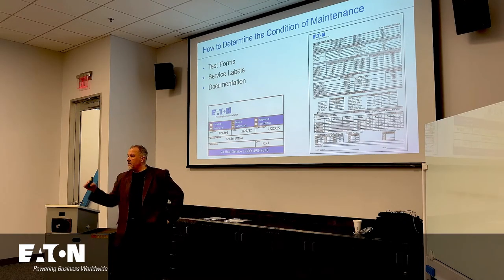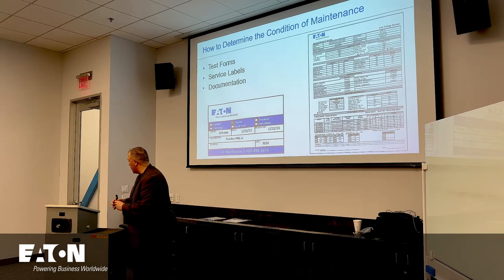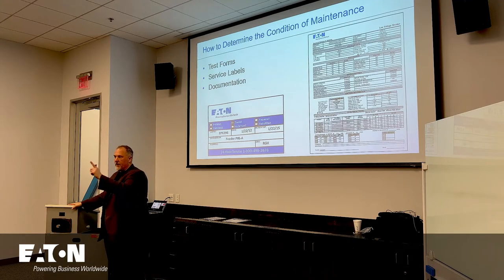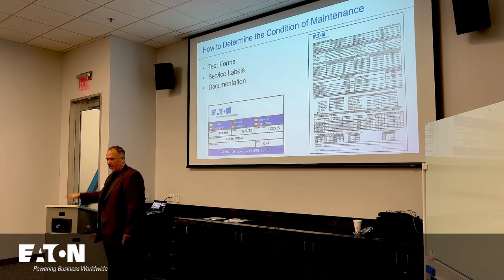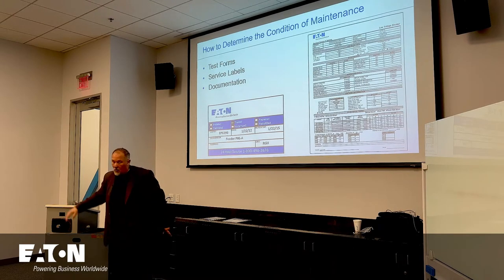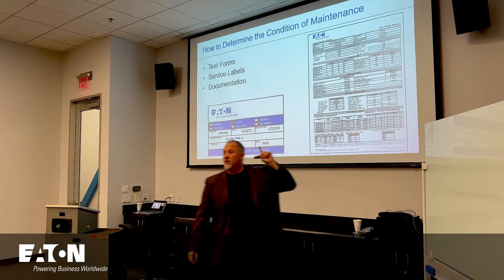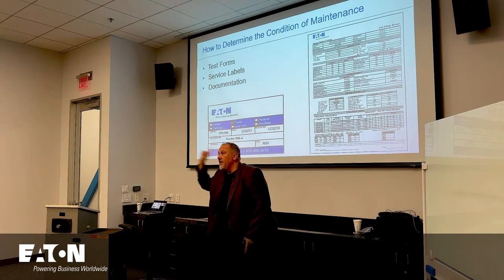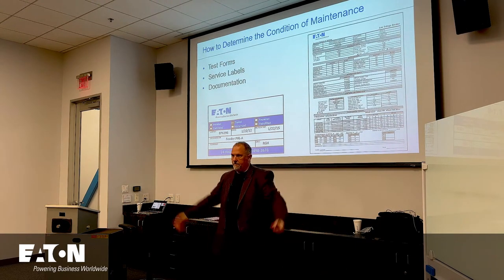The group, whatever piece of equipment you're going to be working on, you're going to look at the equipment, and then you're going to say, what is my overcurrent protective device that's providing my incident energy reduction? It's probably not in that equipment, it's probably supplying it upstream. So you're going to walk over to that equipment. You're going to say, I need the maintenance records on this, and I need the maintenance records on that, and anything in between.